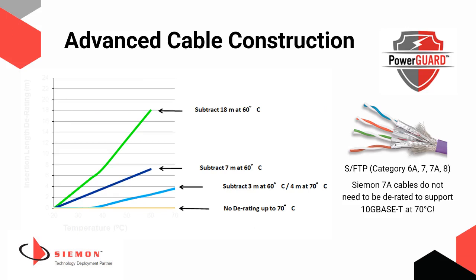This graph shows derating requirements for Siemon's Cat6a and 7a cables compared to industry standard 6a UTP and 6a shielded. But first, let's talk about derating. Heat is the main reason why cables need to be derated. As current passes through the cable, heat is produced as a result of the electrical resistance of the wire. Multiple circuits running in close proximity can further increase the temperature of the conductors as a result of electromagnetic effects and physical proximity effects. When cables are arranged close to each other, cables have limited ability to dissipate heat and reach a hotter operating temperature.